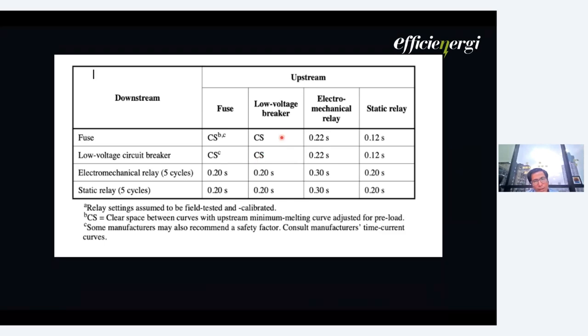But in relays, here you can see the times: 220 milliseconds, 300 milliseconds, 300. This is for electromechanical relays. When we are dealing with static relays, you can see 120 up to 200 milliseconds is required. So that has to be taken care of. But if you have enough data available wherein you specify all the tolerances, then we can have a different CTI as well.